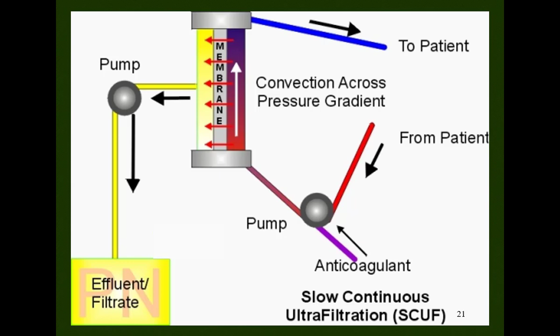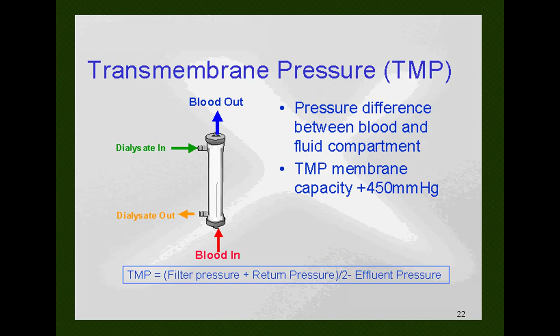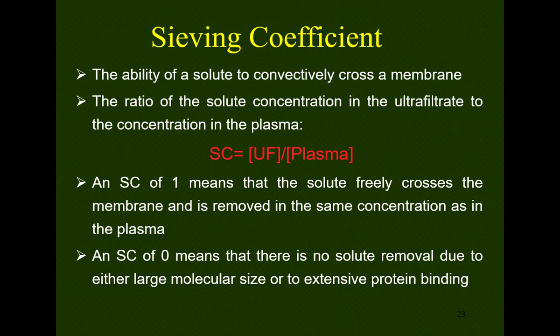So, clear here? Now this is governed by transmembrane pressure, and transmembrane pressure itself is the average of one compartment pressure and the other compartment pressure. The more negative it is, the more the transmembrane pressure would be. If it is more positive on the same side, then again transmembrane pressure would be more. The next thing which governs the clearance is the sieving coefficient. Of course, we can define it, but technically it is purely pore size. Large pore size means more sieving coefficient, small pore size means less sieving.